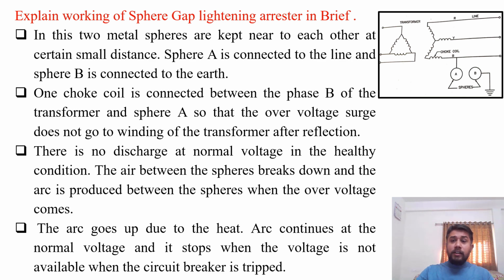So in this, two metal spheres are kept near to each other at a certain small distance. This will cause a sphere gap in between these two spheres. Sphere A is connected with the line and B is connected to the earth. One choke coil is placed in between phase B of the transformer and sphere A so that the overvoltage surge does not go to the winding of the transformer after the reflection like this.